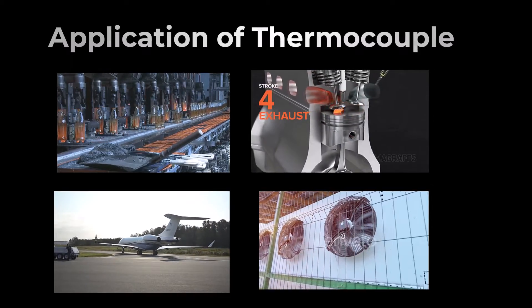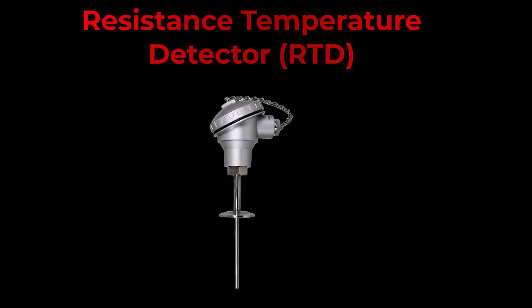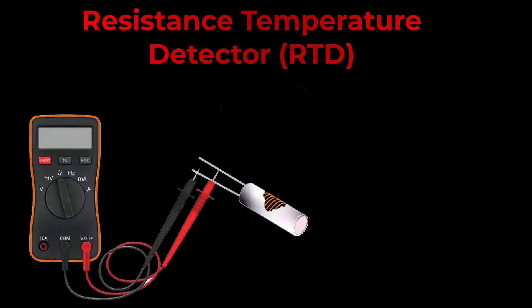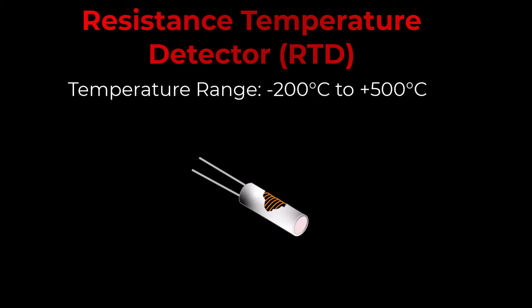Next, meet the RTD — the precision champion. Its correlation of resistance with temperature makes it perfect for laboratories and processes that demand accuracy. RTD stands for Resistance Temperature Detector. It is a type of temperature sensor that measures temperature by correlating the resistance of a metal with temperature changes. RTDs are known for their high accuracy and stability. The measuring range of an RTD lies between minus 200 degrees Celsius and 500 degrees Celsius.